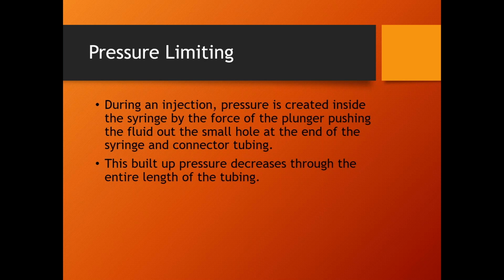And then the third thing, which needs a little more explanation, is something called pressure limiting. Every contrast injector, with one exception, the operator has to select a pressure limit. The pressure limit is the operator telling the injector, do not exceed this pressure, and it's typically in PSI. 99.9% of the time it's PSI. Don't exceed this pressure in the syringe. That's the important part. Don't exceed this pressure in the syringe during the actual injection. Now, a typical pressure limit for CT and MRI injectors is 300 PSI. That's basically the max. Some injectors go to 325 PSI, but in general terms, 300 PSI is the maximum pressure limit that we will allow to build up in the syringe during the actual injection.